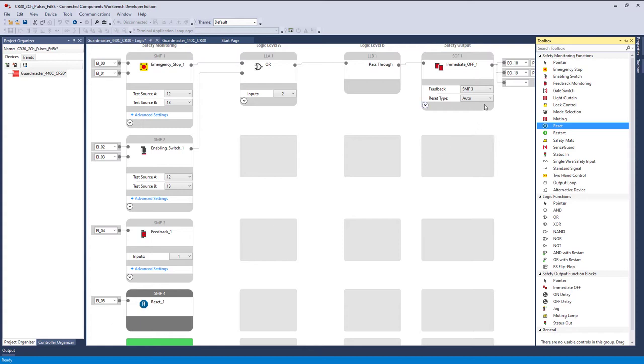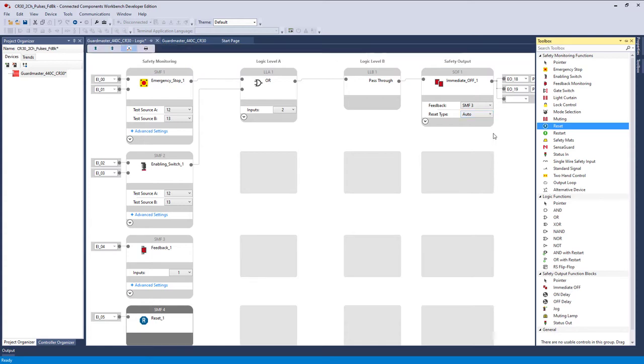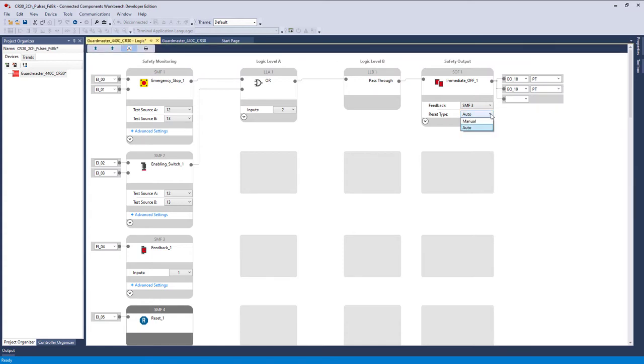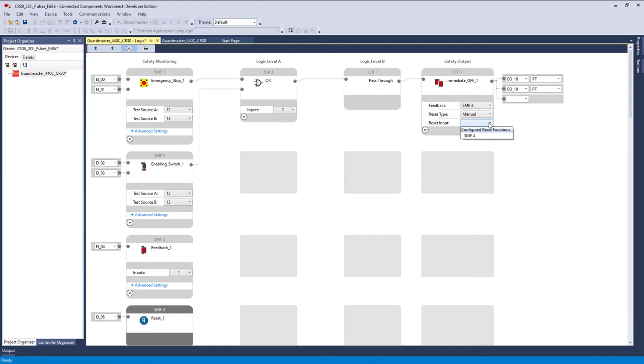The only other thing to do is to go up here to our safety output and switch it to manual, and then it's going to ask, what's your reset input? Well, there's only one that's configured over here, SMF4. If I had not already added this, nothing would show up here. So we select that, and we're done. It's just simple as that. So let's save it.